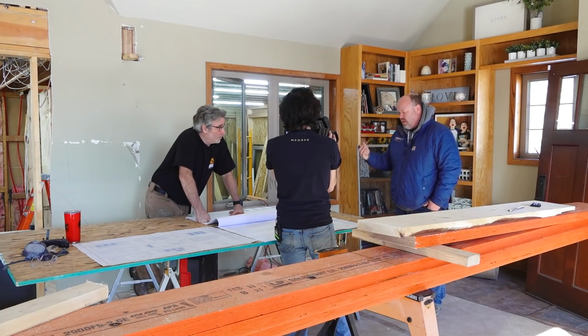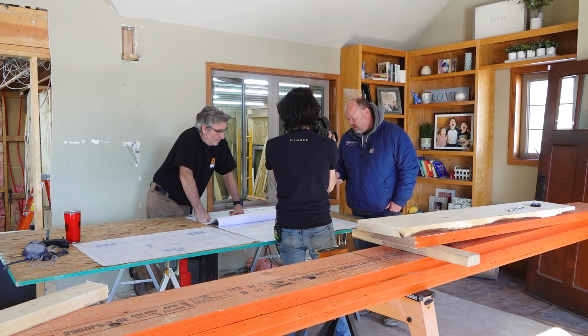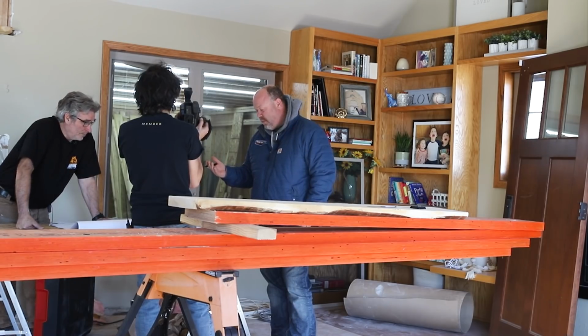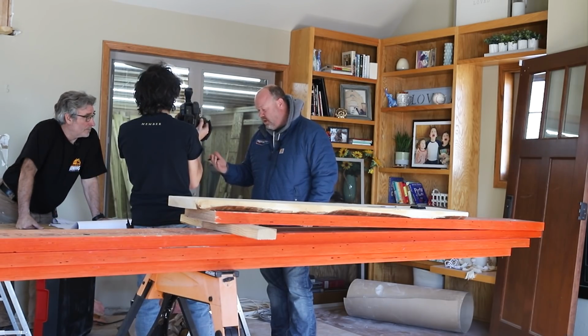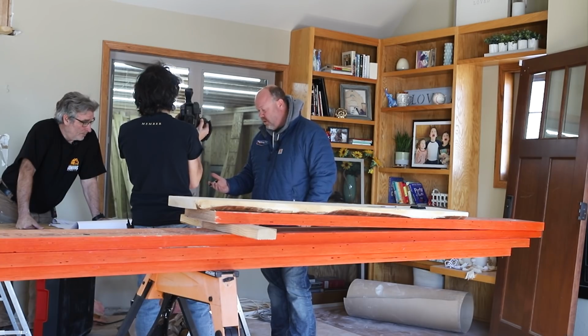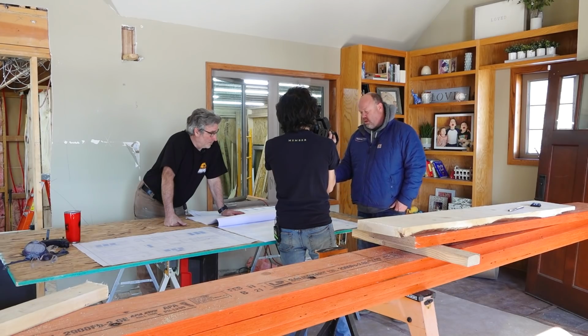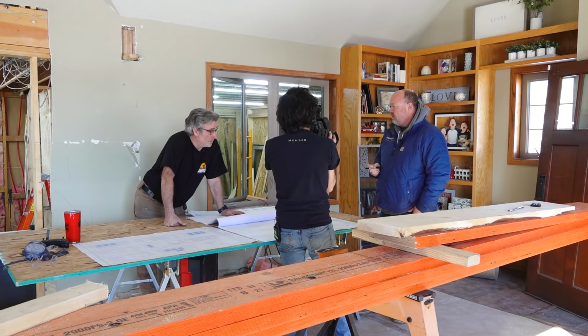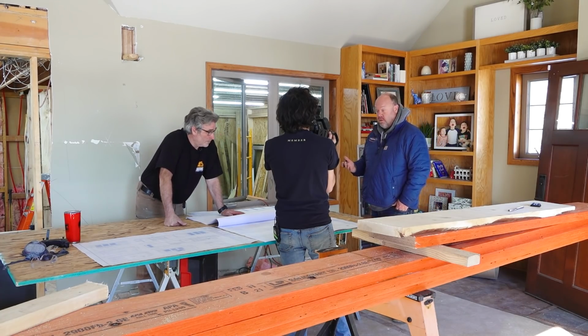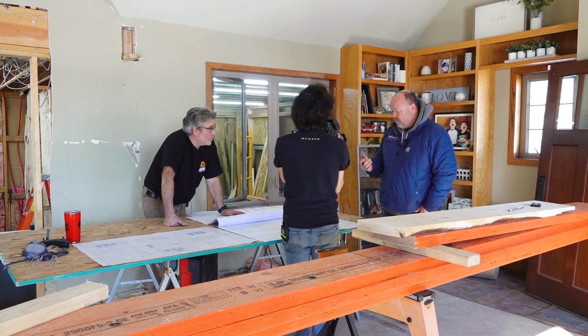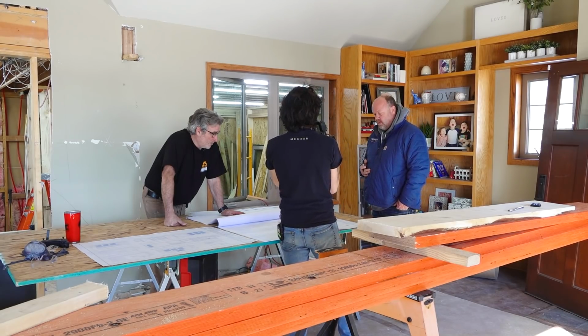So I get a lot of questions on return air placement. Depending on things like 2-story houses or high elevations, if the supply is on the floor, which is very common these days with our construction, we'd like to get the return air as high as we can, right? Pull that heat from the top of the ceiling. With the new equipment these days, variable speed or ECM blower motors, the fan should be running all the time. It's very inexpensive to run. So it really helps promote removing the heat from the top air.